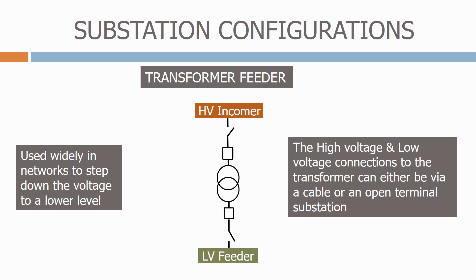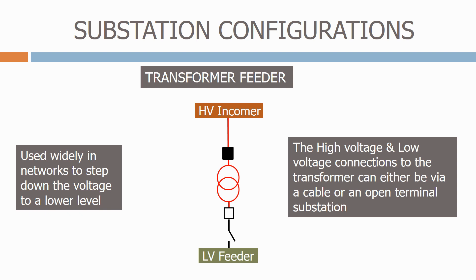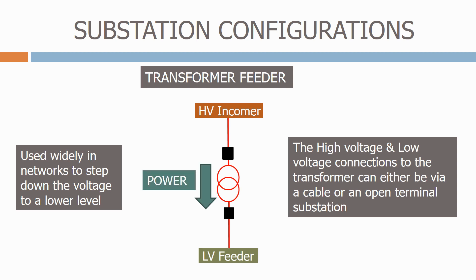Let's see how this circuit works in practice. We can see that the high voltage incomer is now live. We close the isolator on the incomer before closing the incomer circuit breaker, which now energises the transformer. We then close the low voltage circuit breaker — again closing the isolator before closing the circuit breaker. Power is now flowing from the high voltage incomer through the transformer and through the low voltage feeder.